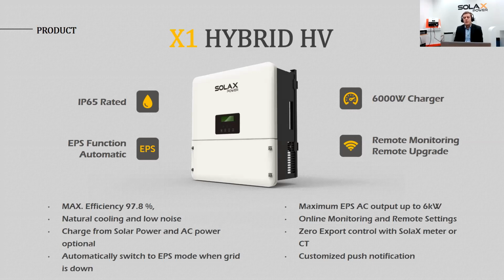You have the option to charge the battery from solar power or from AC power, meaning you can charge it from your usual PV system. But if our meter recognizes some overproduction, for example from a windmill or a heating power station, it will also charge the battery from this power, because everything going out of the system is compared with the demand in the house. If the demand is already supplied and you still have more energy than you need, it goes into the battery first. If the battery is also supplied and you still have overproduction, then it goes to the grid.